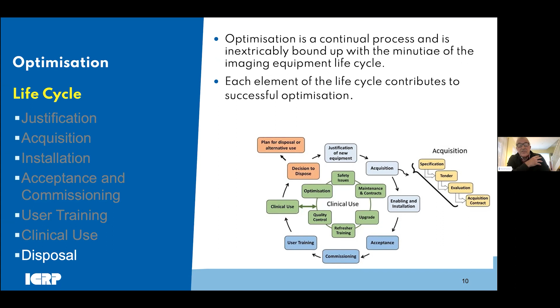So moving on to patient dose. As Colin said, patient dose and its measurement and subsequent analysis is of central importance when it comes to optimization. It's an integral part of much of the equipment lifecycle. We specify dose, we accept against the specification, we use dose as the basis for commissioning, management of dose is part of user training, and we measure dose in QC and use it in dose audit during the clinical phase of the life cycle.